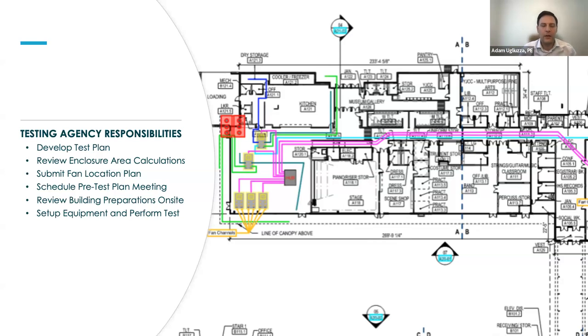And that's going to tell you the allowable CFM that you can have to be able to achieve a pass test. You need to be lower than that. So it's a very important calculation, and that's why really the testing agency shouldn't be doing it. It should be the designer doing that, because it does affect a pass or fail for the test. Submit a fan location plan.